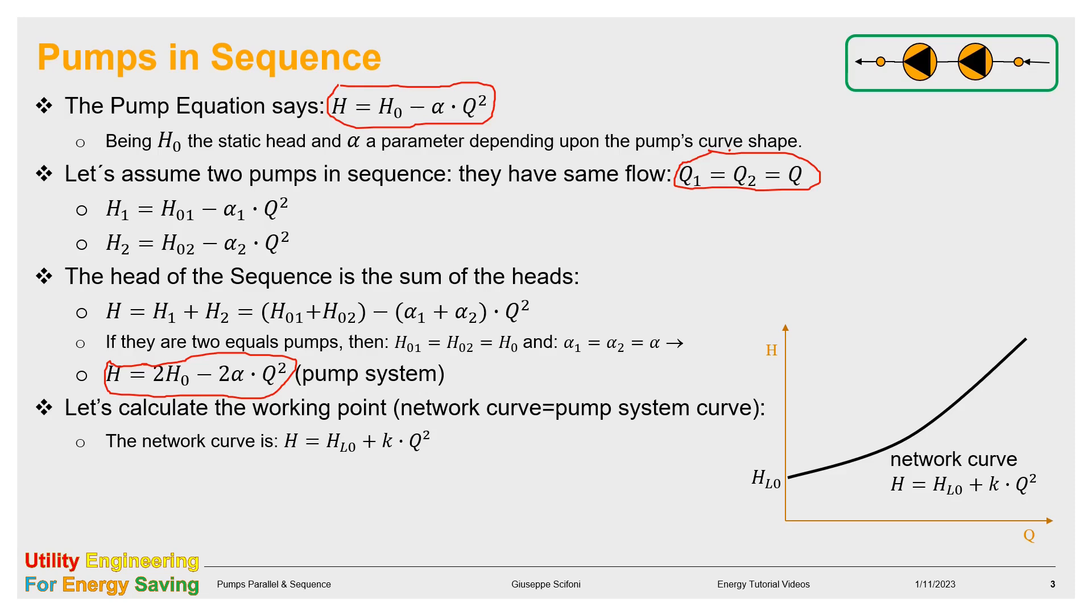The network curve is still a quadratic function with the shape of an ascending parabola instead. That curve depends upon two parameters: the head at zero flow HL₀, and the curve shape K, that describes how deep the curve is. The above parameters are also given. The intersection point among the two curves is found by equalizing the two equations. We get Q as the flow for the sequence and H as the head of the sequence, as displayed in green.